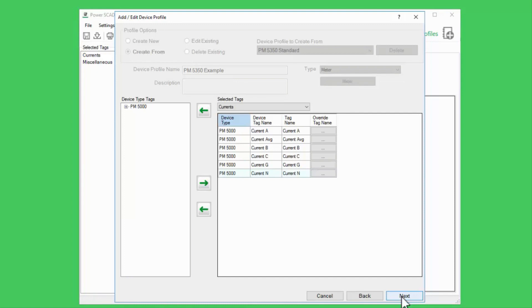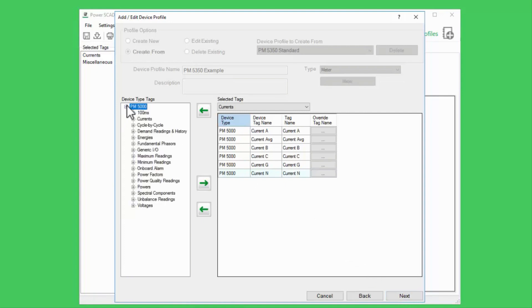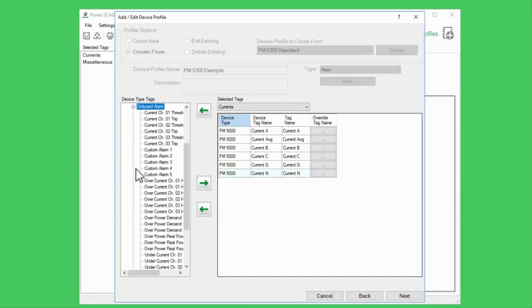The big difference this makes in profile editor is there are no checkboxes to create onboard alarms. Rather, there are specially configured variable tags in a group called onboard alarm that are designed to read values from an event log and write them to the alarm server. We'll discuss these variable tags in more detail as we cover the different drivers, but for Modbus devices like this, the onboard alarms are generally only valid for factory device types and can't be created custom.